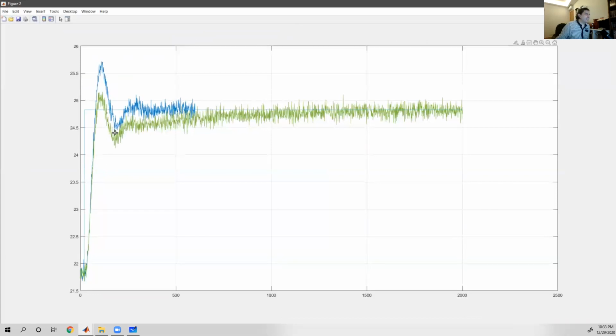Now, as you can see, we reached the set point, but it takes a very long time. So what I would like to mention here is about the tuning of PI control parameters. Now, the good thing is the integral action has a very small overshoot. That's great, but then the increase to the set point is very slow. So there's a trade-off, not very easy to understand, between Kc and tau I values from P-only control and integral control.